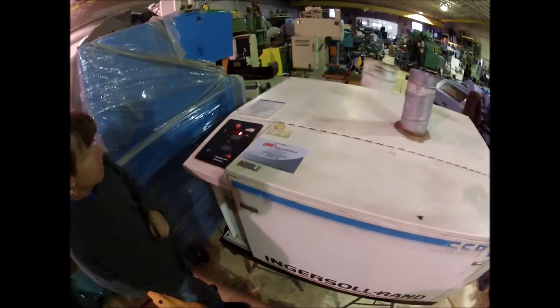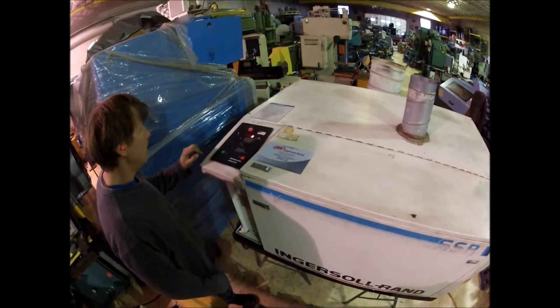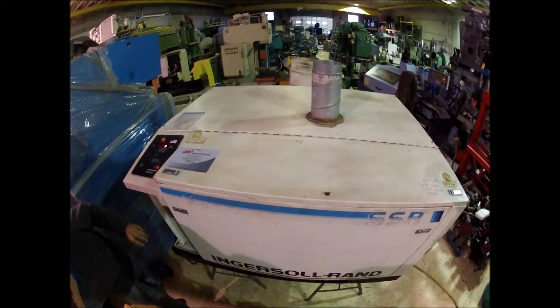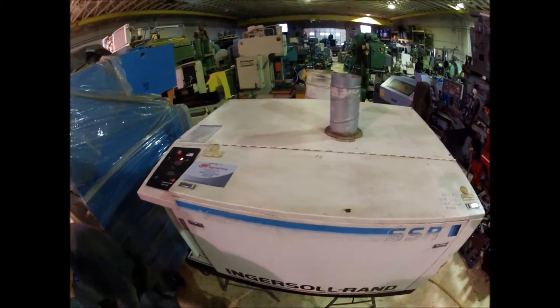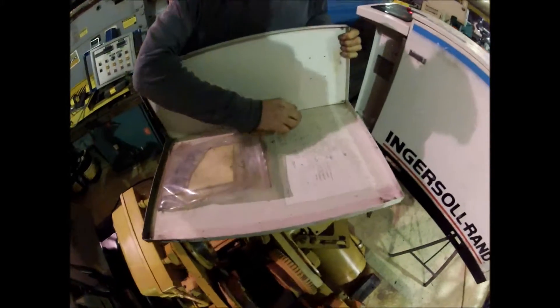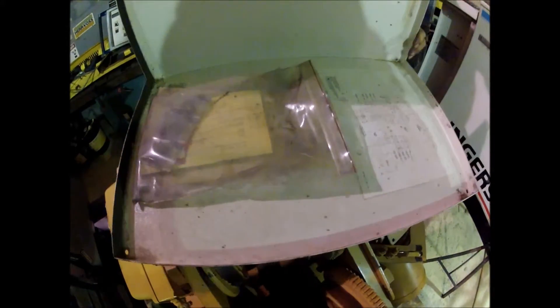It's got an oil cap here. The side cover is off on this thing right now. It has a wiring diagram here, and it has heaters in here for 440 volts. Right now it's wired 220, for changing it over to the higher voltage.